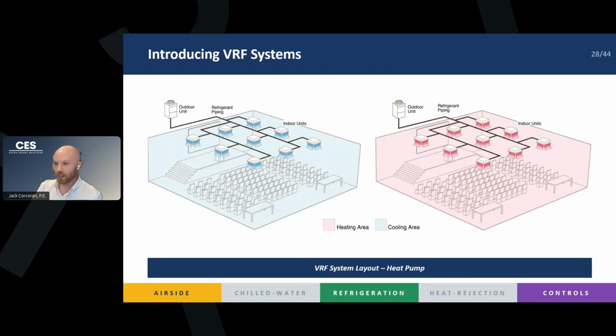So what does this look like? We're going to take a high level view of this first. Essentially, if you look here, we'll have 3 or 4 main components to our VRF systems. It's going to be our indoor units, right? These are the devices that sit in our occupied space. We're going to have outdoor units that sit outside. These actually reject the heat into the ambient air. And we have refrigerant piping that connects all of it, right? Somehow that heat needs to move from the indoor units to the outdoor units. That medium is the refrigerant piping. In this situation, this is a heat pump VRF system where all of our units are heating or all of our units are cooling. The outdoor unit is just going to switch between heating and cooling modes.